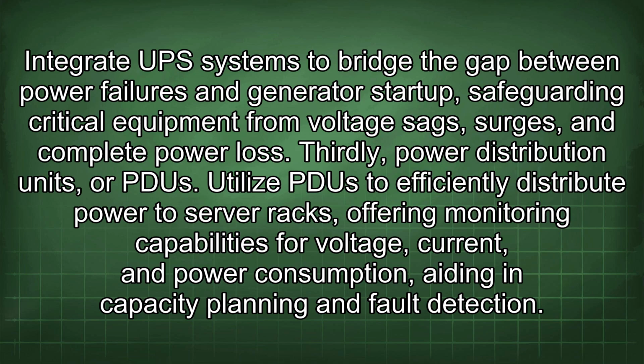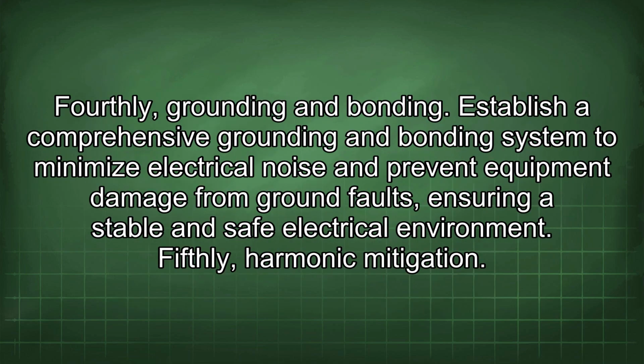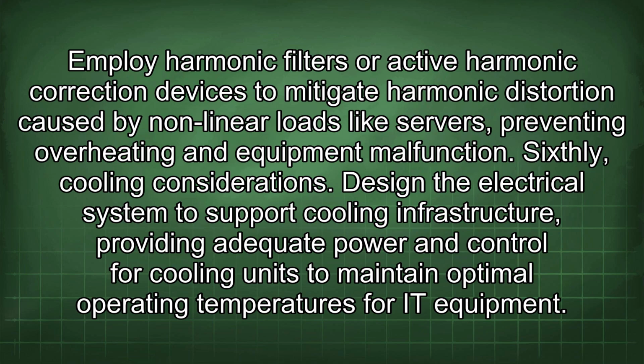Utilize PDUs to efficiently distribute power to server racks, offering monitoring capabilities for voltage, current, and power consumption, aiding in capacity planning and fault detection. Fourthly, grounding and bonding. Establish a comprehensive grounding and bonding system to minimize electrical noise and prevent equipment damage from ground faults, ensuring a stable and safe electrical environment. Fifthly, harmonic mitigation. Employ harmonic filters or active harmonic correction devices to mitigate harmonic distortion caused by nonlinear loads like servers, preventing overheating and equipment malfunction.